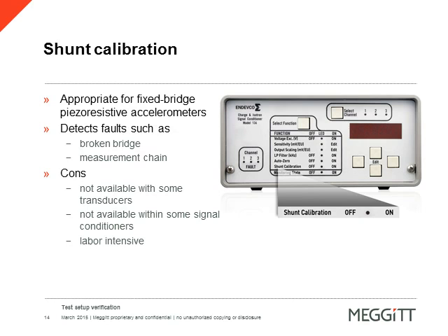For instance, shunt calibration. Shunt calibration can be performed as another verification test for piezoresistive transducers, channel setup, gain setting, and proper cable connection. Shunt calibration is a physical connection of a calibrated resistance value across one non-active Wheatstone bridge leg. Some transducers have internal shunt resistors installed for quick and easy testing. Shunt calibration is a simple and potentially accurate means of simulating action of a strain gauge.